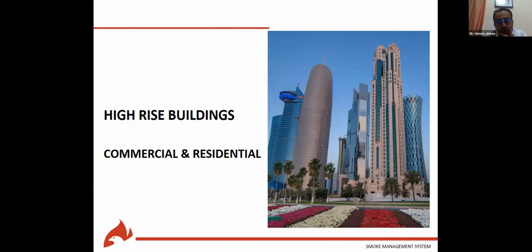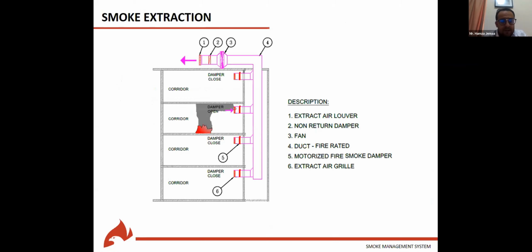The application of the smoke control in the high-rise building and commercial residential building. As you can see here, this is an illustration of a tower in which there is a smoke in the corridor. The system in place for smoke extraction shows that the smoke is extracted from the floor in which there is a fire, and the sequence of operation will be once the fire alarm detects the smoke, a motorized smoke damper will open in the floor in which there is the fire, and on other floors the smoke damper will be closed. So the hot gases will be extracted using the duct system to outside.